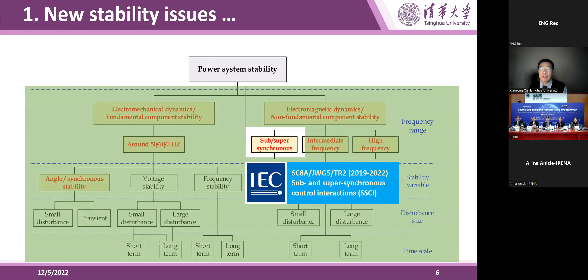Let's look at SSCI events in real-world power systems. For more than a decade, power systems around the world have experienced emerging wideband electromagnetic oscillation in converter-dominated power systems, with frequency ranging from a few hertz to more than 1,000 hertz—for instance, subsynchronous oscillations, supersynchronous oscillations, and higher frequency oscillations, which can be collectively called wideband oscillation.